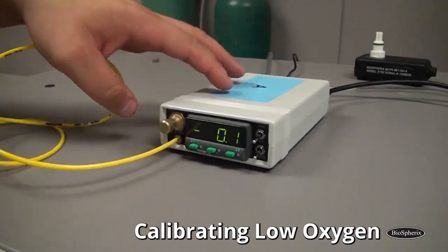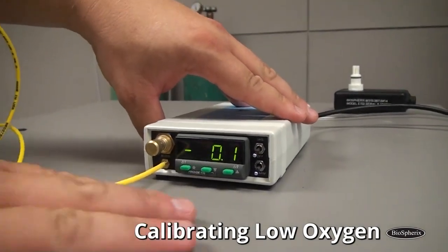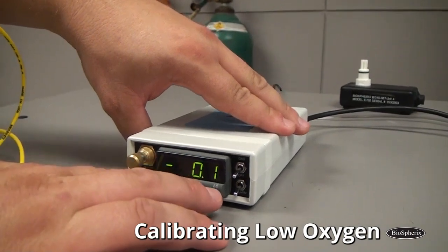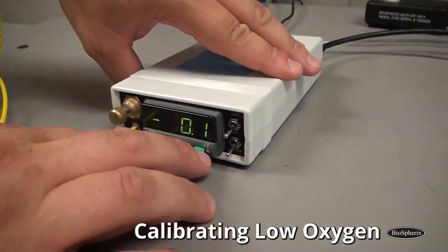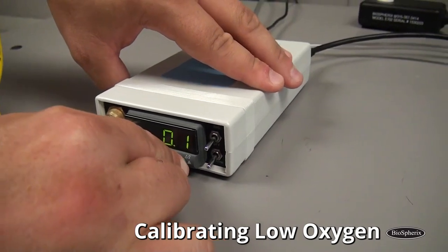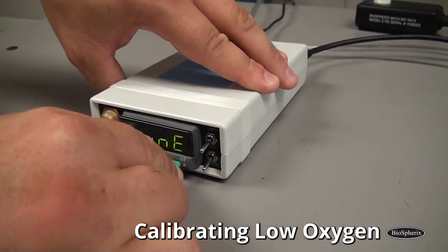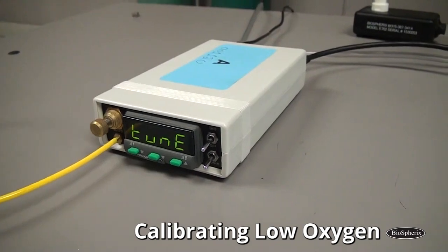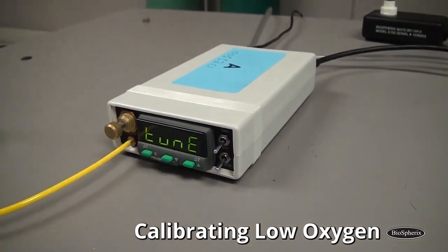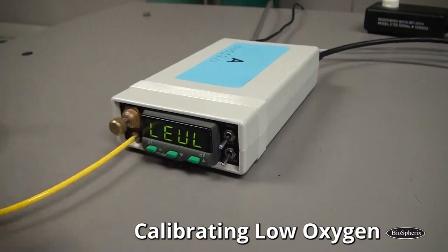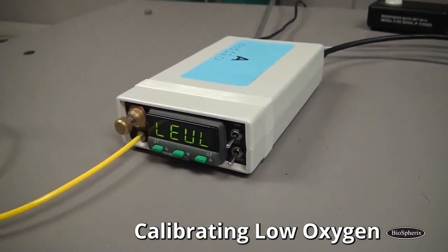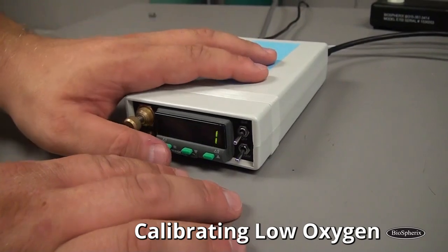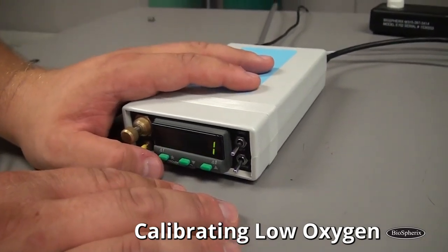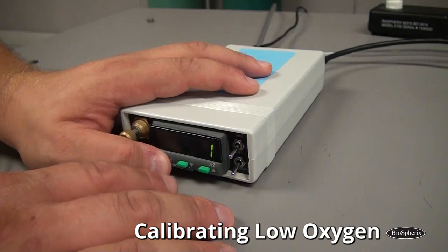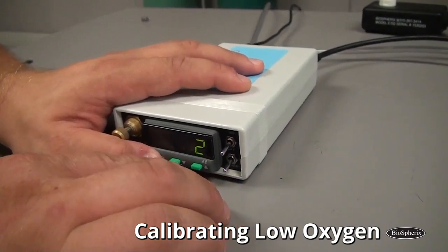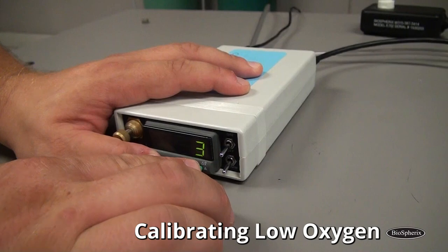And to do that, I need to go into the program mode on the controller. Everything's found in level 3 on the controller for calibration. So I'm just going to hold the up and down for 3 seconds until I see the word tune and off. Now I know I'm in the program mode. So I press down once to get to the level function. And I need to change it to level 3. So if you want to make a change to a function, you hold the star, and while you hold the star, you can press up or down. So you can change through the different options.